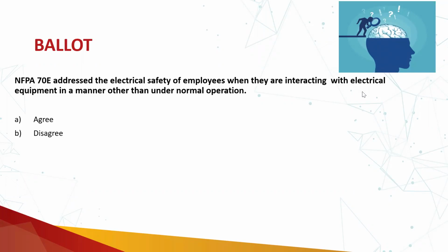There is no requirement to create an arc flash boundary or shock protection boundary. There is no requirement to carry out the risk assessment, shock risk assessment, arc flash risk assessment, and the person performing the job is not required to wear any PPE as well. It's not even required to fill out an energized electrical work permit. So if the equipment is under normal operating condition, those are not required. But if the equipment is considered under abnormal operating condition, then 70E requirements come into action, which is about safe work practices defined in the standard. Yeah, this question and explanation is clear.